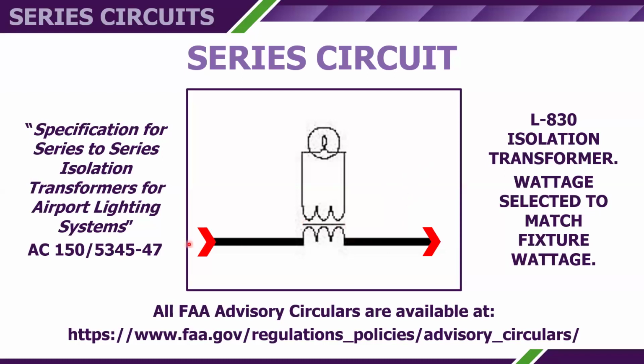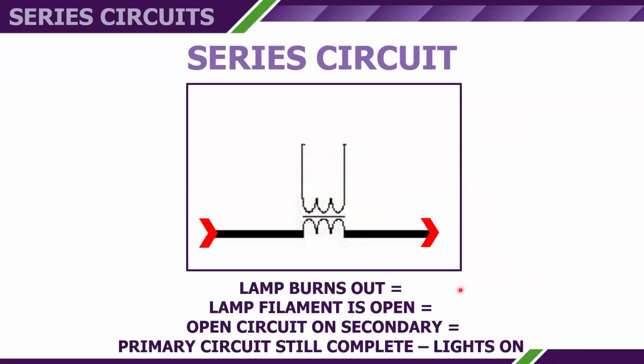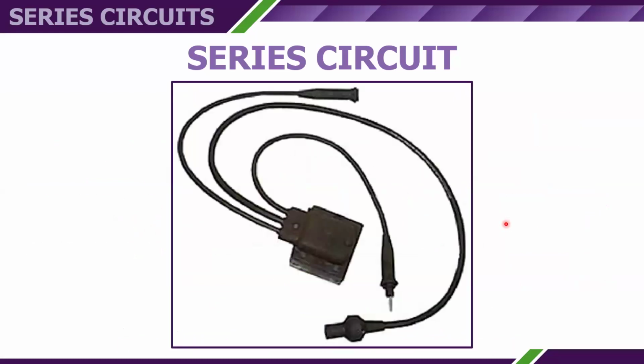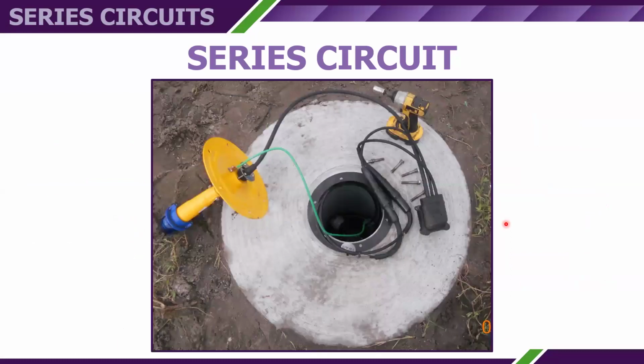So you see here, our primary circuit goes through the primary coil in the transformer. It stays continuous. If we have a light burn out, the primary loop is still continuous. The secondary circuit in that transformer opens, but the primary current still works. All the other lights stay on. This is what an L-830 isolation transformer looks like. This is the transformer in the field attached to the fixture.